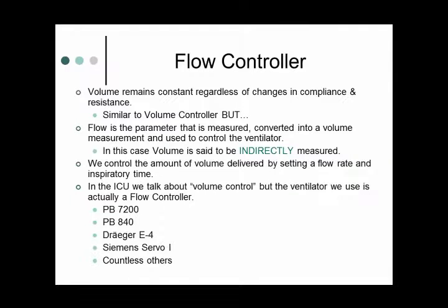You said dual mode is usually pressure control? Dual mode, the mandatory breath utilized in a dual mode is a pressure-based breath. It's a pressure-controlled breath, unless it's specified otherwise. You can set up any of those ventilators either as a flow controller or as a pressure controller. The software allows that.